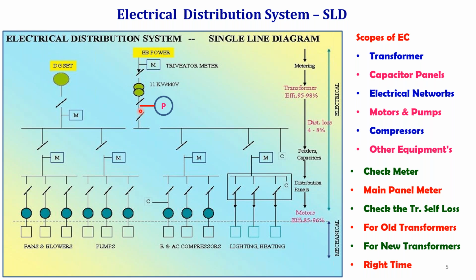So if you estimate the transformer loss, even for an old transformer or a new transformer, then automatically we can come to a conclusion whether we have to change the transformer from an older to a newer version. If it is a newer version, then you can check whether the promised energy loss at different load conditions is ensured. So that is a good idea. You have to check whether your equipment is working properly, as per the design. That is why we insist on taking the readings at the panel board side, secondary side and similarly the primary side at regular intervals simultaneously, so that we can estimate the transformer losses.